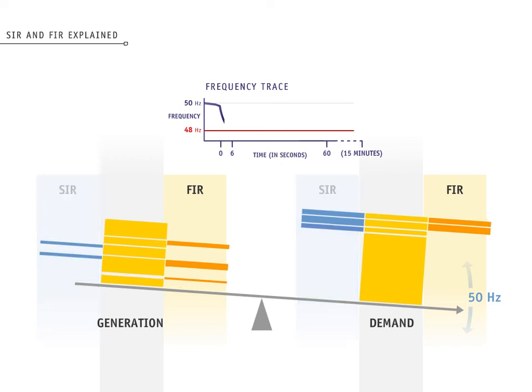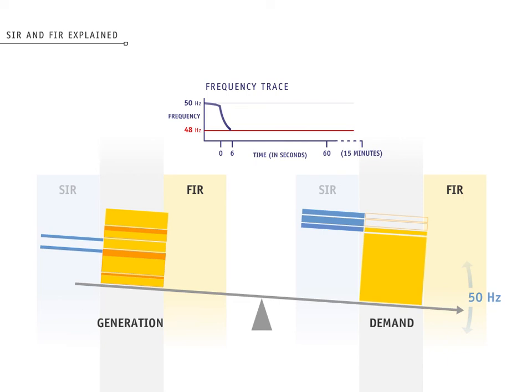The fast instantaneous reserve kicks in within 6 seconds and acts like a brake to prevent frequency going below 48 Hz, but is only required to last for 60 seconds.